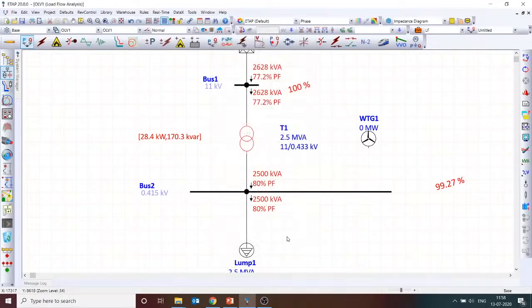If I want to plot kVA and power factor, you can plot it. The power factor on the LV side is 0.8, but the power factor on the HV side is further lower, at 0.772. The power factor is given in percentage, so 80% means 0.8 power factor. The metering is available on the HV side, where the industry is connected, at the point of common coupling. There they measure the maximum demand as well as the energy consumed, along with the power factor, and if there is a poor power factor, they will put a penalty. The power factor is now 77.2%.